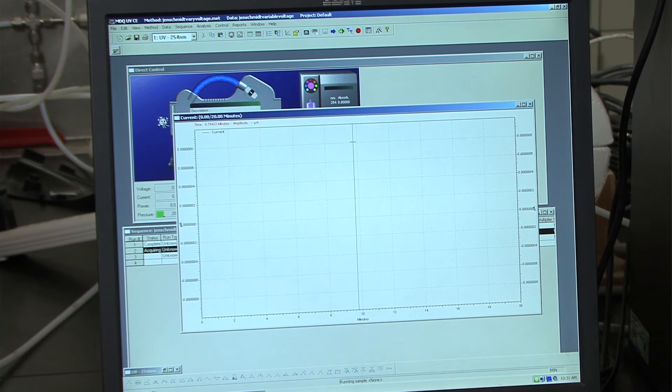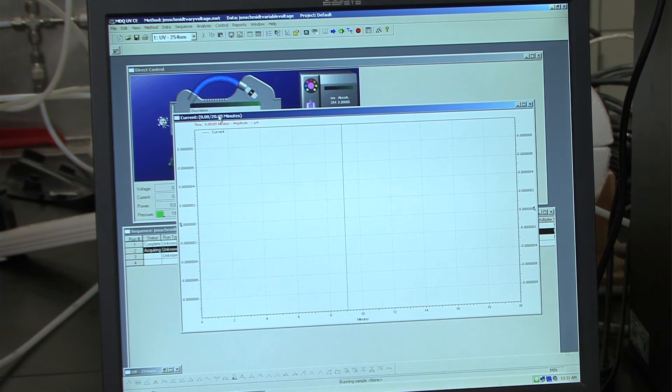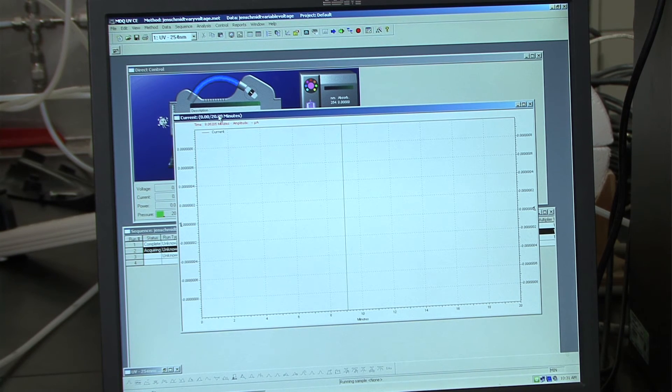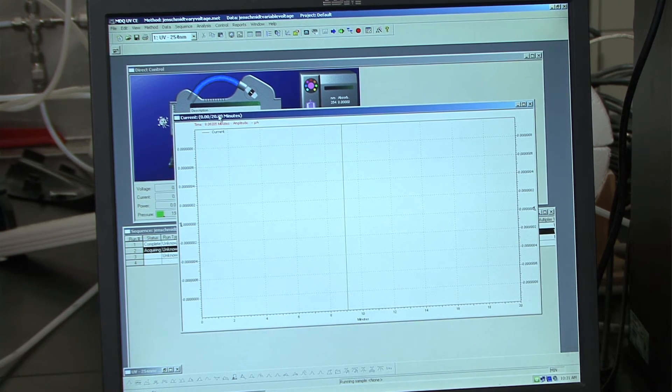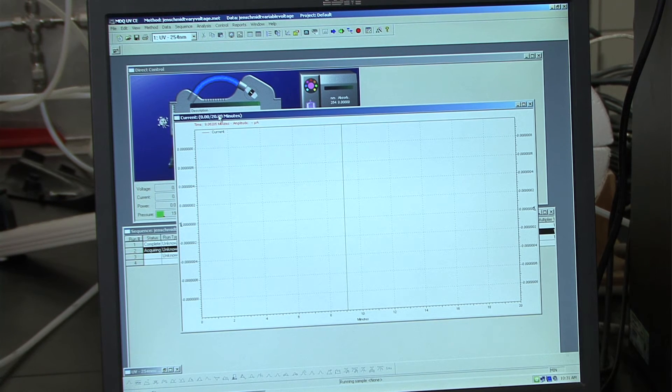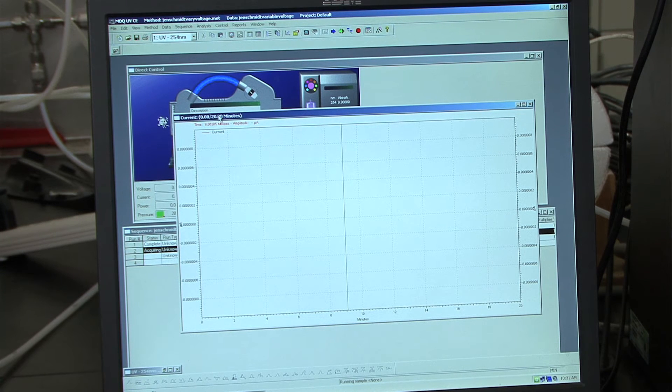When your first sample has been injected, you will notice this window pops up. And throughout the sequence, you will notice that there will be a sort of step type graph. If you don't have a step type graph, that indicates that the instrument is not working properly.